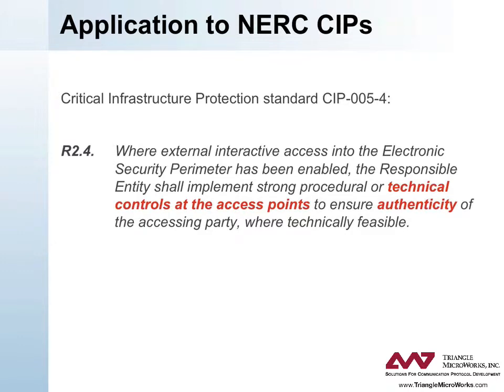The question that many utilities ask is where does DNP3 Secure Authentication fit with respect to the NERC CIPs? Firstly, as of this writing in July 2014, the mandate of NERC applies only to the bulk electrical system — that is, transmission. So in theory, distribution networks, where many DNP3 deployments are found, are not affected by the CIPs by definition, though this may change in the future. Secondly, some people make the argument that DNP3 is not a routable protocol and therefore does not need to be secured. That may be true of DNP3 over serial links, but it is certainly not true of DNP3 over IP, because IP, by definition, is a routable protocol. It's not clear how it applies when DNP3 is transferred from an IP network to a serial or radio network.